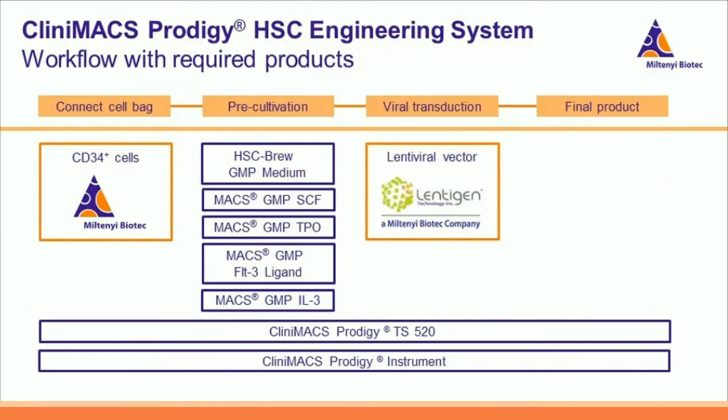Here I show the required material of the HSC engineering workflow, divided into connect cell bag, pre-cultivation, viral transduction, and harvest of the final product. In the purple frames you see the Miltenyi backbone part, whereas the orange frames depict the flexible part of the system. The Miltenyi backbone includes the CliniMACS Prodigy instrument and the CliniMACS Prodigy tubing set TS520, as well as the culture reagents for the CD34-plus cells — HSCBrew GMP medium and MACS GMP cytokines: SCF, TPO, FLT3 ligand, and interleukin-3. The flexible part includes the CD34-plus cells enriched beforehand using either the CliniMACS Plus or CliniMACS Prodigy, and the lentiviral vector — which can, for example, be purchased from Lentigen.